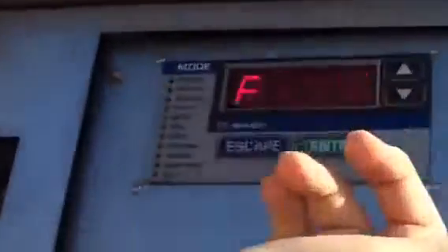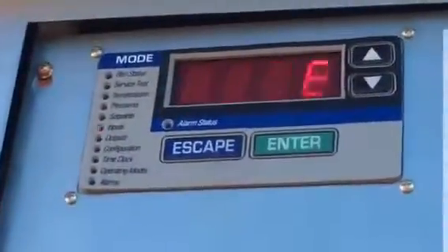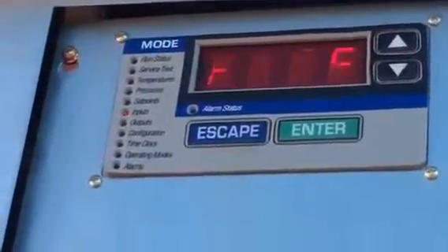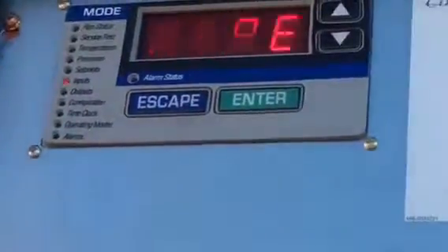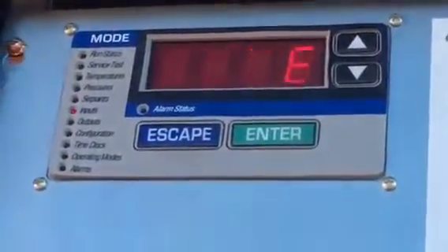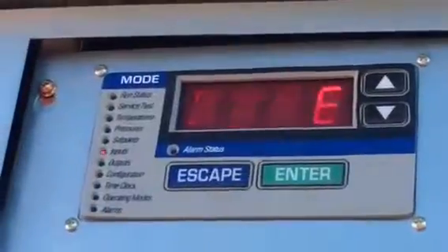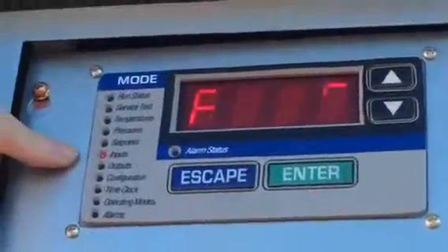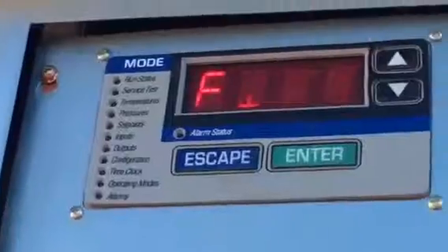And that's things like, let's back out. I have inputs and outputs. I can always choose to see what kind of inputs the machine is looking at and receiving. On inputs, I can hit enter, general I, feedback, status, fire shutdown. Like if these have been set up for fire shutdown and I have a unit that's sitting there not running, I can always go in, status, one of the HVAC modes is going to be fire shutdown. So right off on my view that scrolls by always, it'll tell me why it was shut down, fire status. So the fire damper shut, causing the unit not to run. Or I can always go down here to inputs and see that I had that fire shutdown command.